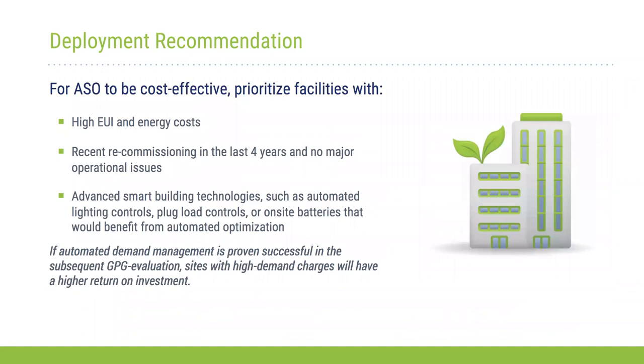For deployment recommendations, this product could be cost effective and we can install it in other areas. However, we might want to test it in areas with higher EUIs and higher energy costs, because as we saw, the cost effectiveness for Texas wasn't the greatest, but that doesn't mean it won't make large impacts somewhere else where energy isn't as cheap, or where EUIs might be higher in buildings that are inefficient for whatever reason. We also want to see retro-commissioning within probably about the last 4 years, just to make sure you're not dealing with garbage in, garbage out, since this is a software system.